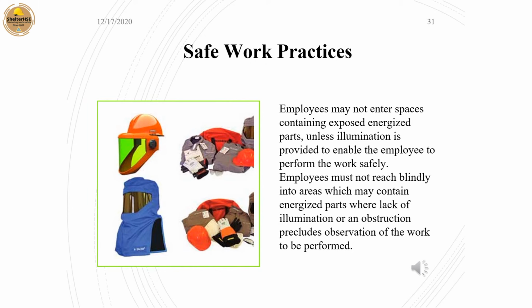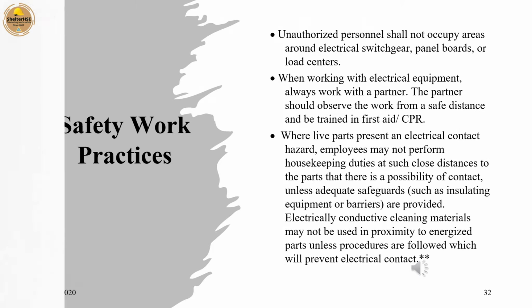Employees may not enter spaces containing exposed energized parts unless illumination is provided to enable the employee to perform the work safely. Employees must not reach blindly into areas that may contain energized parts where lack of illumination or an obstruction precludes observation of the work to be performed. Unauthorized personnel shall not occupy areas around electrical switchgear, panel boards, or load centers.